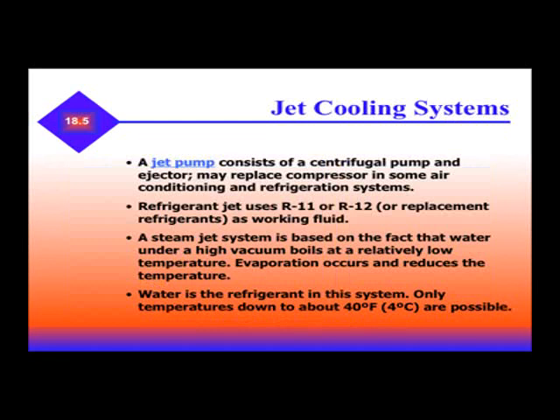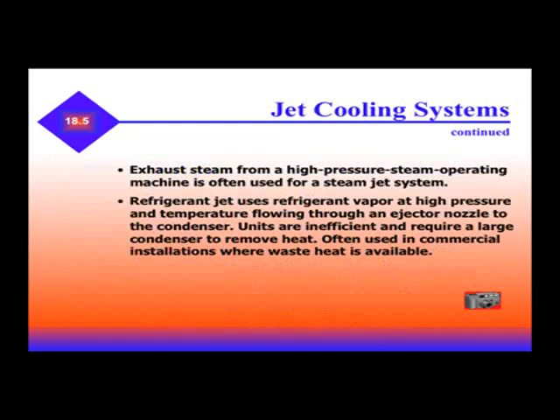Jet cooling systems are also used. A jet pump consists of a centrifugal pump and ejector, and it may replace the compressor in some air conditioning and refrigeration systems. Refrigerant jets use R11 or R12 as a working fluid. A steam jet is based on the fact that water under a high vacuum boils at a relatively low temperature. Evaporation occurs and reduces the temperature, and water is the refrigerant in the system. Only temperatures down to about 40 degrees are possible. Exhaust steam from a high pressure steam operating machine is often used for steam jet systems. The refrigeration jet uses refrigerant vapor at high pressure and high temperatures flowing through an ejector nozzle to the condenser. Units are inefficient and require a large condenser to remove heat, and are often used in commercial installations where waste heat is available.